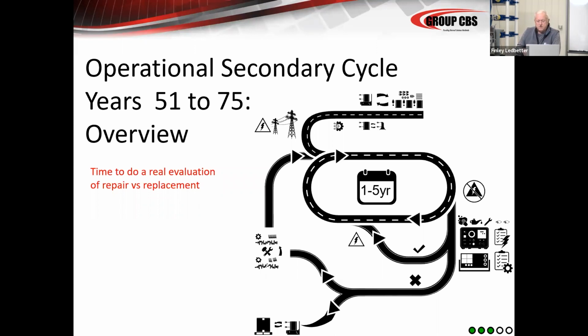The problem is disturbing the cables. These cables are now 50 years old, and 50-year-old cables don't like to bend, don't like to move. So if you disturb the cables, the chances of damaging a cable are pretty great. That leaves you with having to possibly tap from that existing cable, leave the old switchgear in place, and tap jumper cable from it over to the new gear. Now you've got two more joints. Those joints are normally not shielded. It's normally jumper cable. So you have all kinds of long-term issues there. So we'll talk about that in the fourth segment and the properties of doing that.